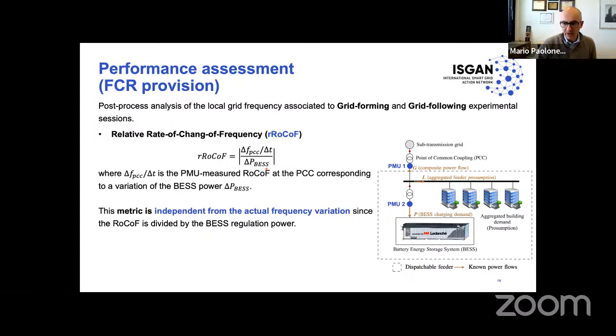So here I'm showing you the cumulative distribution function of this relative RoCoF. On the horizontal axis, you have the hertz per second per watt, so the relative RoCoF, and on the y-axis, you have the probability. You see 4 cases. Case 1, 2, and 3 are for a grid forming control unit. Case 4 is for a grid following control unit.